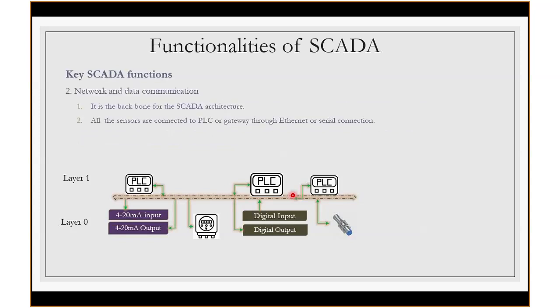The next one is the network and data layer. This is the backbone of the SCADA architecture. Without network, without communication, nothing will work out. All the sensors are connected to the PLCs or gateway via either Ethernet or serial connection. Most cases nowadays everything comes under Ethernet. Maybe in legacy SCADAs or legacy sites, we have serial communication like Modbus or RS-232 based customized communication. In those locations we might use gateways and converters to connect that serial connection to the Ethernet connection. So it's a general practice that any serial communication needs to be converted into TCP/IP at the least level.